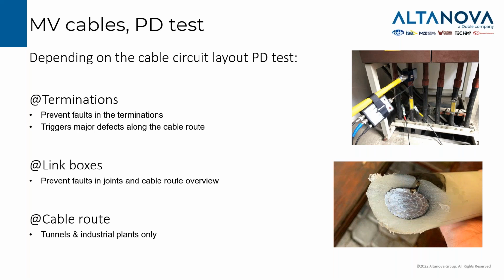And we can also trigger major defects coming from the cable. So we can see that there is a signal of PD coming from the cable route, even if we cannot exactly localize it. We can manage this information to be used accordingly for the maintenance planning. In some other cases, if we have very long lines, we can have even in medium voltage some link boxes. So we can test partial discharge from the link boxes as well, and we can cover the cable route in a more accurate way. In some rare cases like tunnels or industrial plants, we have the whole cable route accessible, so we can test the whole cable circuit even if it takes, let's say, a little longer time because we have to follow all the cable. It can be very, very effective.